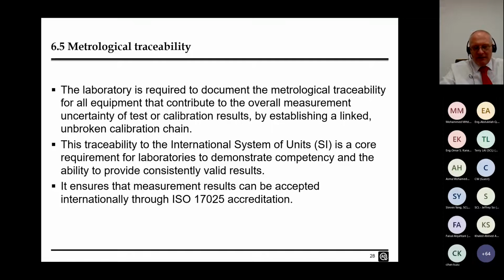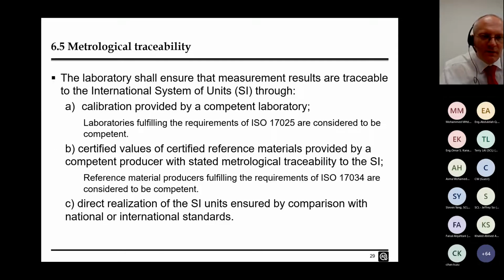Through the ILAC MRA, your accreditation body will have been accepted, and anybody who's accredited by them can provide calibrations anywhere in the world. And through the CIPM MRA, the NMIs with published CMCs on the KCDB can provide calibrations anywhere in the world, and they will be accepted. But this is all based on traceability back to the SI, because that's the core technical requirement for that.